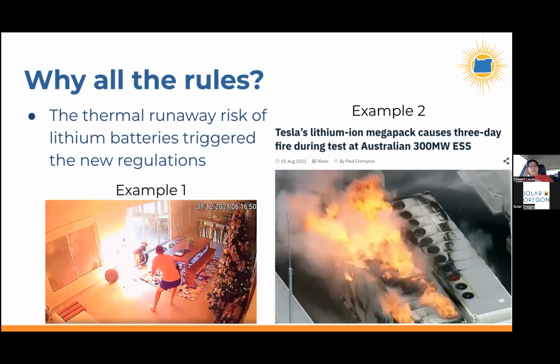So what I mean by that is, a defect in the cell. Often the cause is metal shavings, typically from the manufacturing of the cell, and that metal shaving landed in a spot in the cell that it shouldn't, and that causes a short circuit. And from the short circuit, you end up having heat generation when that cell gets charged. That heat generation causes a thermal runaway, and then one cell overheats and catches on fire or overheats adjacent cells, and then those go into thermal runaway, and it becomes a domino effect.